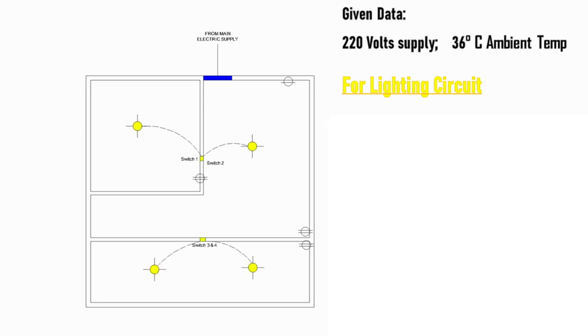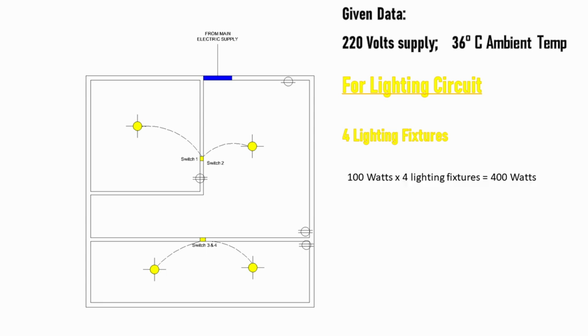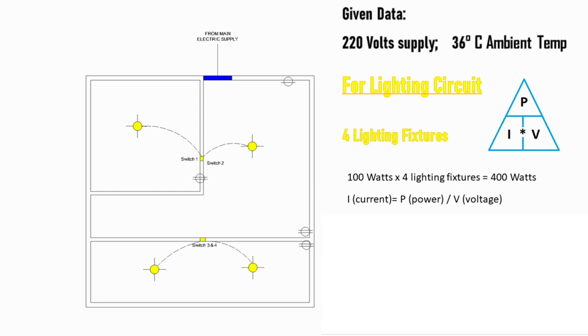For the lighting circuit, NEC states that 100 watts shall be the maximum load for each household lighting outlet. Adopting 100 watts per lighting outlet: 4 lighting outlets × 100 watts = 400 watts. Applying Ohm's law to get the required current: Current = Power ÷ Voltage = 400 watts ÷ 220 volts = 1.82 amperes.